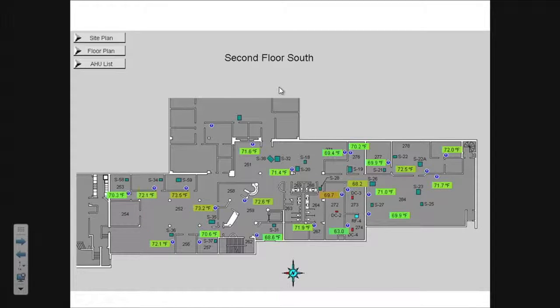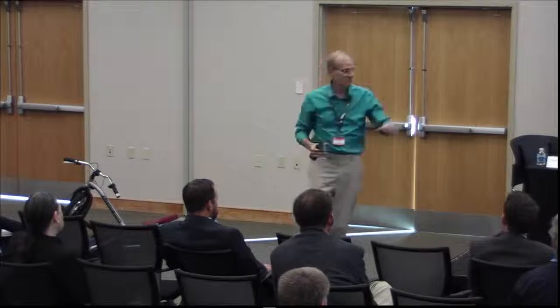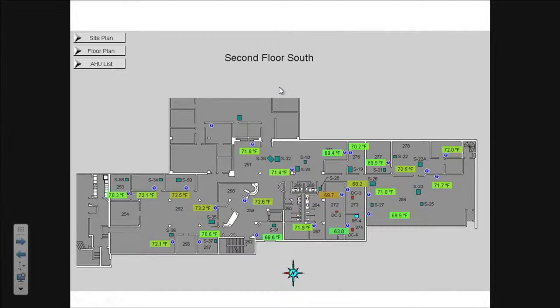Every little square you see on here is a thermostat. Back of the wall, there's a thermostat there, there's a thermostat there. And each one of those controls modulates the space temperature by reducing the outside air. So this is a 3D printed box that Oak Ridge National Lab printed out for me. It has a damper on this end, so cold air comes in and it reduces the amount of outside air if the space is getting colder and colder, but it stops because it doesn't want to go too low, because then you wouldn't have enough fresh air for ventilation in the space.